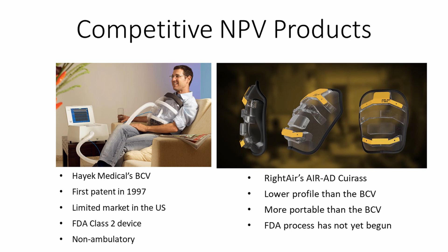Quick comparison of cuirass ventilators in general versus the conformal vest ventilator. A cuirass ventilator has a rigid shell which does not move with the body. This makes it difficult to seal leakage, especially along the sides, and it interferes with motion, bending over or twisting motions in particular. There's a large volume of air under the cuirass, and changing that pressure means high energy consumption, which in turn means that if you're going to make it portable, you need a big battery. In fact, the Hayek Medical device is not portable in that sense. It has to be plugged in.